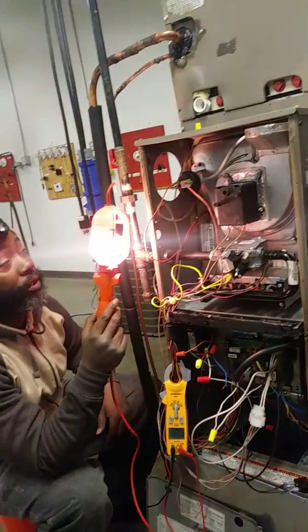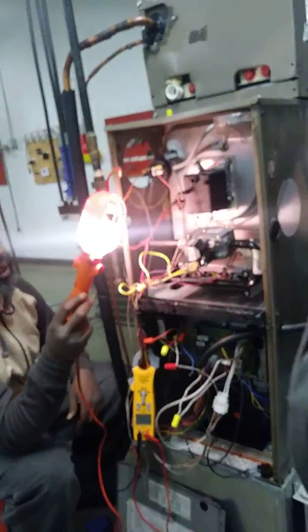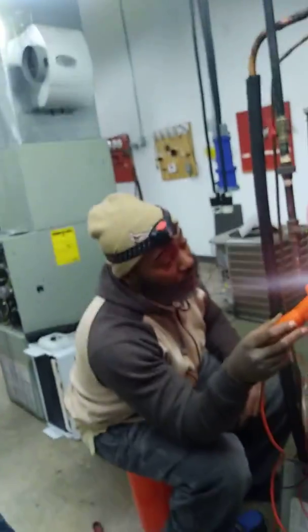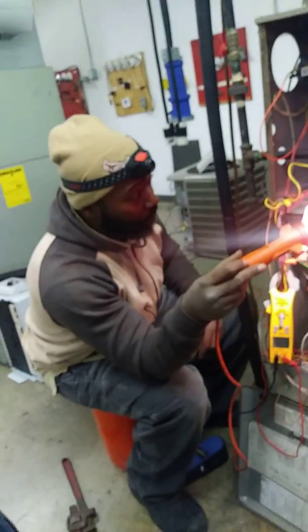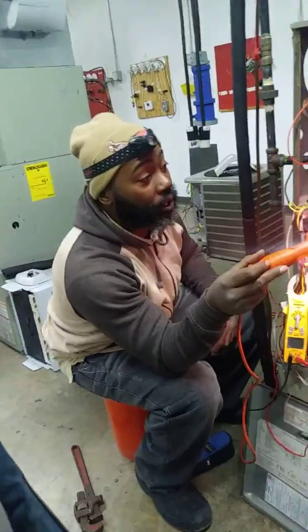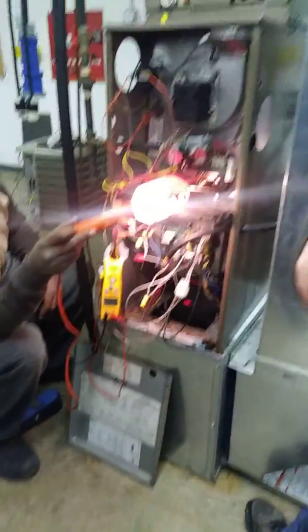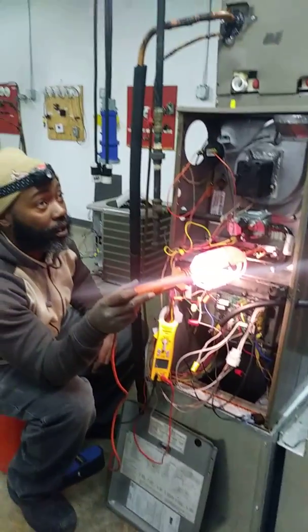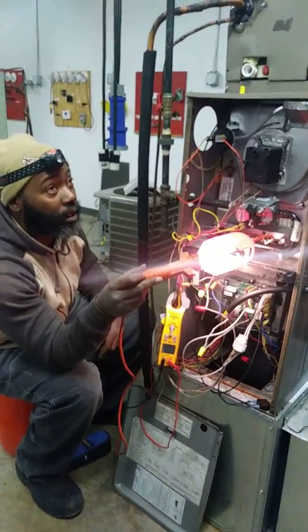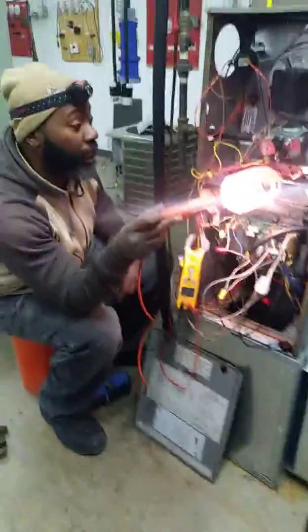What's second after the inducer motor? The pressure switch. The pressure switch has to close. The rollout and the limit have to be closed. If those are not closed, you're not going to get the hot surface igniter. But it may pass the hot surface igniter. Right, the hot surface igniter lit up.